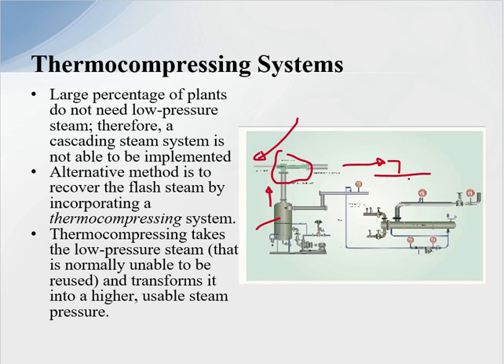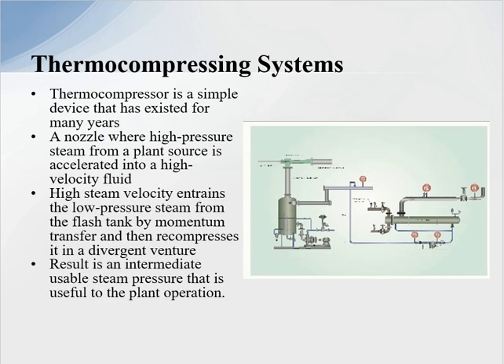Basically, the thermal compressor takes low pressure steam that is normally unable to be reused and transforms it into a higher, usable steam pressure we can use in the process. The thermal compressor is a simple device that has existed for many years. A nozzle accelerates high pressure motive steam to a high velocity, which entrains the low pressure steam from the flash tank by momentum transfer, then recompresses it in a divergent venturi, resulting in an intermediate usable pressure that is useful for plant operation.